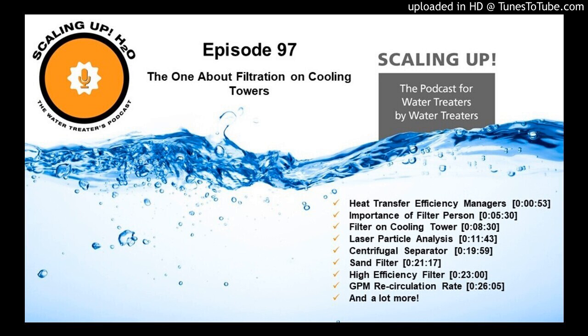We had to dial that in because we were not able to concentrate the water up to where we knew that water needed to be. It was backwashing more than it really needed to, and we weren't able to get the concentration ratio up to where we wanted it until we made some adjustments. That's a problem that occurs when the tower filter uses the tower water for backwash.